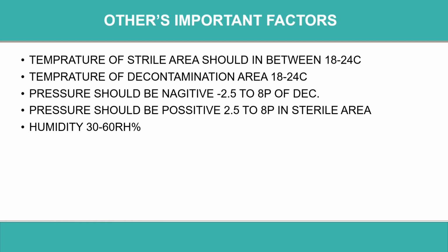Why do we require negative pressure? Because if we open the door, the outside air should go inside the negative or decontamination area. If the decontamination air went out when we open the door, it would contaminate the other environment. So we require negative pressure in the decontamination area. Vice versa, we need positive pressure in the sterile areas, so that when we open the door, the air goes outside. Humidity we require 30 to 60%. It is mandatory, because in this temperature and humidity range, 30 to 60%, the fewest microorganisms will grow.